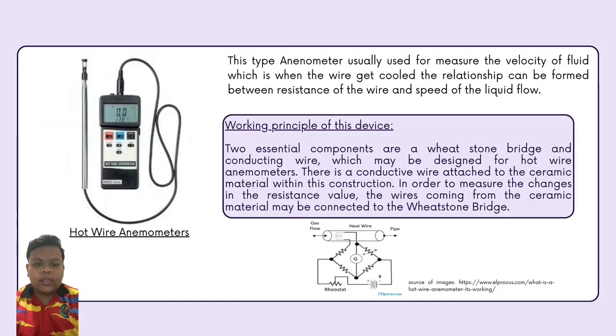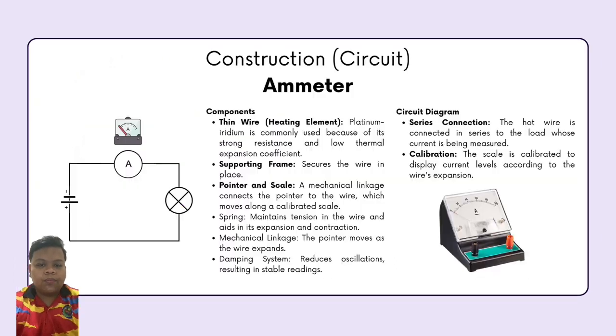The second device that uses the hot wire type system is the hot wire anemometer. This type of device is usually used to measure the velocity of fluid. The principle is that when the wire gets cool, a relationship can be formed between the resistance of the wire and the speed of the liquid flow.